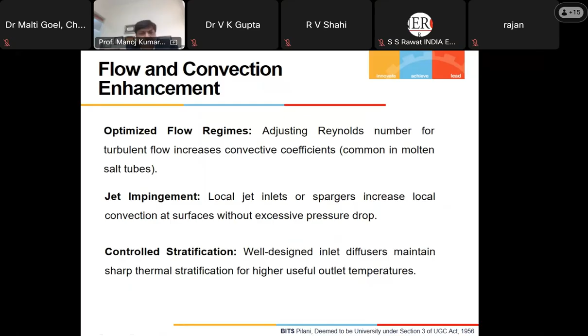Controlled stratification, with a well-designed inlet and diffuser, can maintain sharp thermal stratification for a higher useful outlet temperature. This is specifically where a single tank is used for both hot storage and cold storage.